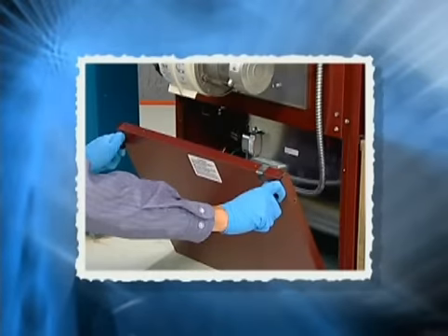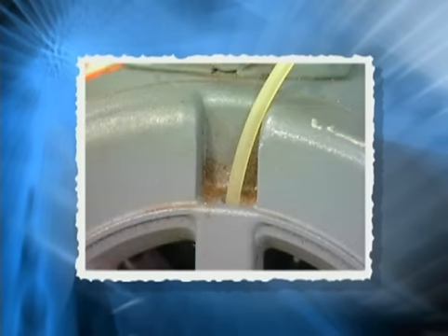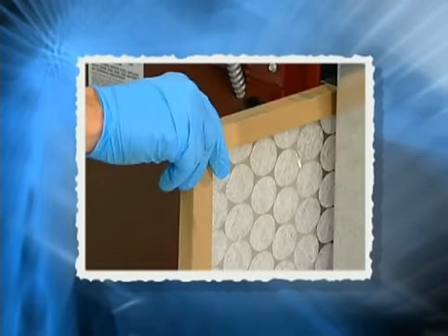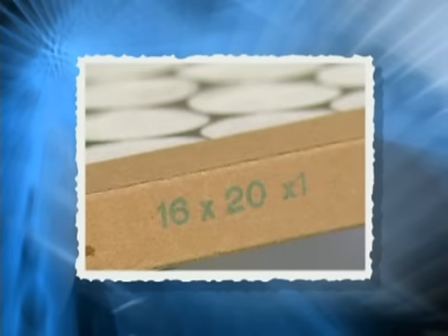Open the blower compartment to check the blower and lubricate it if applicable. Check the air filters and replace them from the customer's supply. Note the filter size on your service ticket and remind the customer to check and replace the filter regularly.